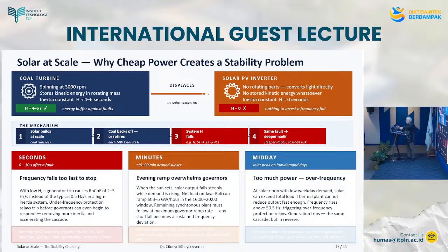And then after that, the governors of the steam turbine will come in and increase the energy input, so it will keep going at 3000 RPM, right? What I'm saying is that it will not lose the spinning 3000 RPM within the first 4 to 6 seconds. It will keep turning. And then to keep going, the governors will act and open the inputs, and there will be more fuel coming in, and then it will generate more steam, and it will keep going, okay?